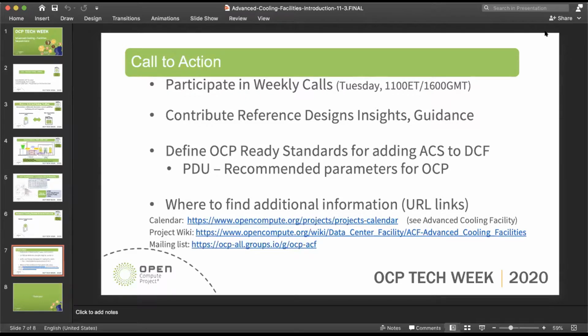Exactly, so it's something that should be respected but not feared. However, as Jessica was highlighting, if you're working with cold plate and immersion, generally those can operate at temperatures well above any dew point you'd see in a data center. But it can vary a lot by region too. Some regions have greater humidity in the air and a higher dew point; others are low humidity with a lower dew point, so it's not a risk factor for them. But it's a great question.